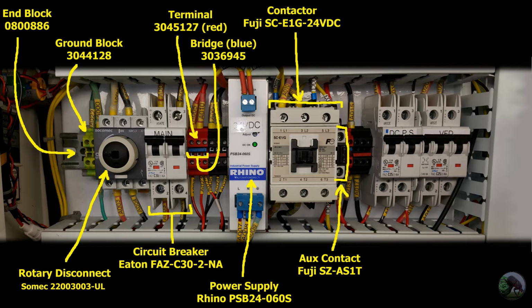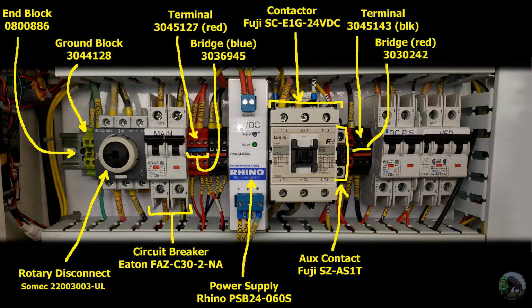And this has a normally open pair of connections and a normally closed. So basically, anytime the contactor changes state from open to closed, it takes this auxiliary contact with it. And so since two of the connections here on the auxiliary contact are normally open, they basically just close, and then the normally closed ones open. So you can use that to signal, and in my case, they are participating in the latching circuit, which we'll get into later. All right, next up is just the black terminals, pretty much identical component to the other one.